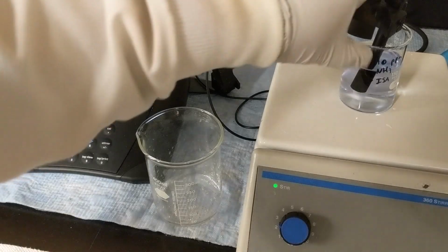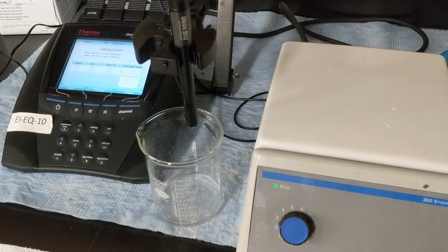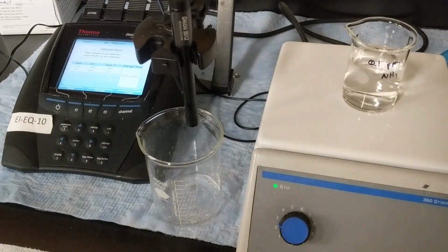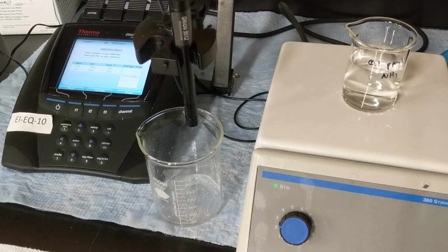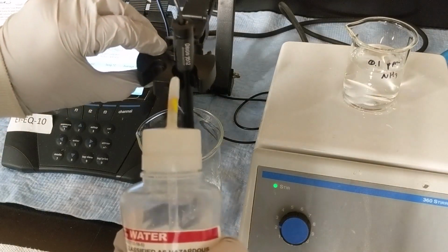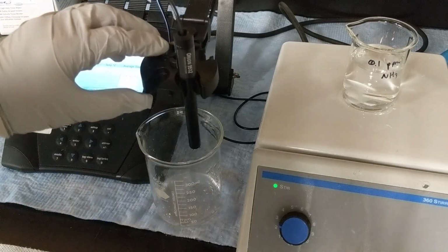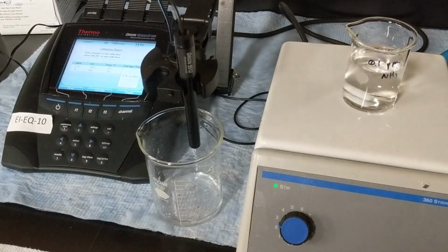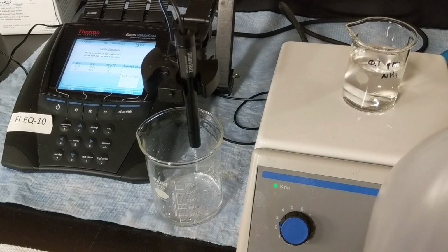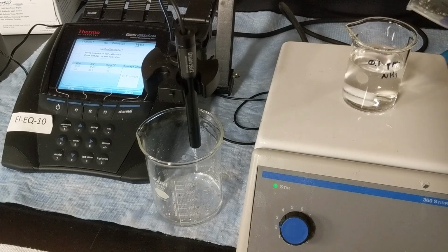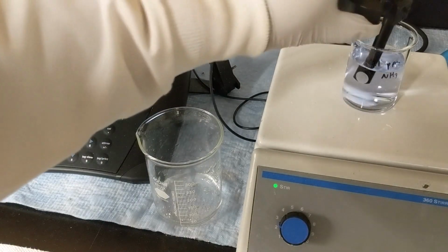So now what we can do is do a little measurement, and the measurement is done in very much the same way as the calibration. So I have now another 0.1 ppm solution of ammonia. I'm going to put another stir bar in. I'm going to rinse off the probe. Put in my 1.5 milliliters of ionic strength adjuster. Insert the probe into the solution.